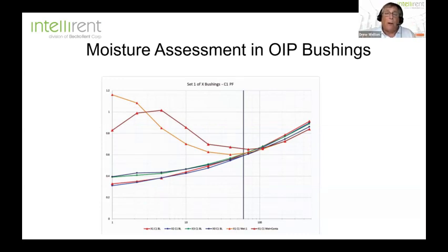The one point I want to make here is that doing this extended power factor measurement is also relevant to oil filled bushings. Once you can take your C1 test and extend down the frequency like we did before, you can see an indication of moisture in the bushings themselves. And that's one of the most damaging things there is to OIP bushings.